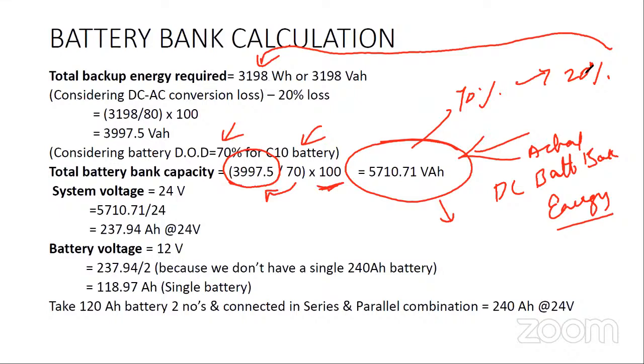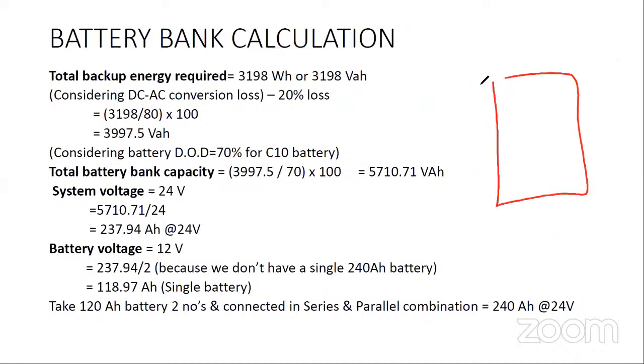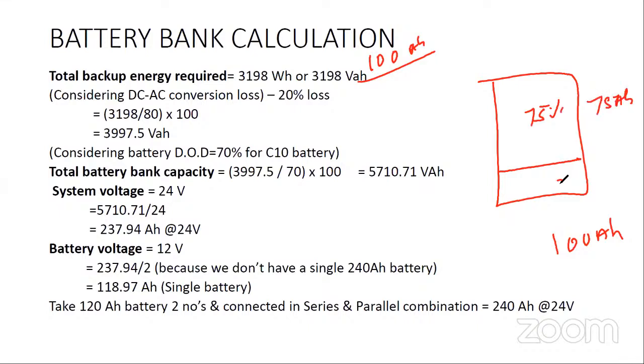So depth of discharge is how much of the battery you are able to discharge. Let's say you have a 100 Ah battery, and you need 100 Ah equivalent of power to be delivered. You should not choose a 100 Ah battery for a 100 Ah requirement. The problem is you can only discharge 75%, which means you can probably discharge 75 Ah of energy, but 25 is still left. So if you want to discharge 100, then you need to have more than 100. That's why the 25% is left.